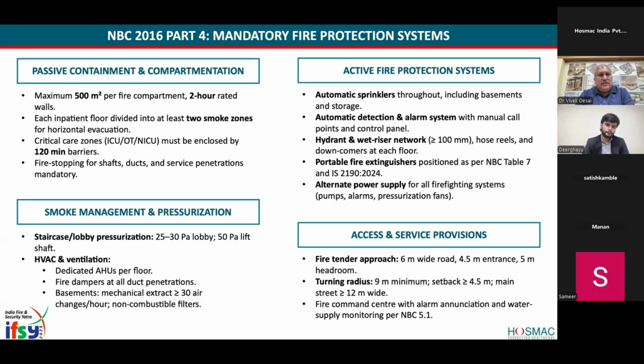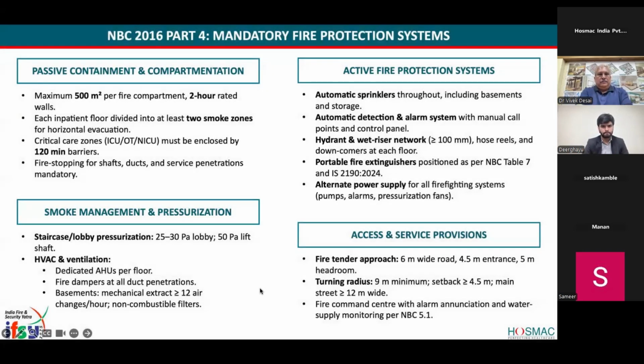So you should have fire dampers and all of that he mentioned. In basements, mechanical extract of more than 30 air changes per hour, non-combustible filters. Is there anything you want to say about basement exhaust, Satish? Yeah. So for basement exhaust, I think it is revised to 12 ACPH, not 30. Okay. Normally there will be smoke exhaust systems at 12 ACPH, and fresh air is also required as makeup for supplying oxygen to occupants. And normally the CFO keeps on asking, despite mechanical ventilation being given, for natural ventilation also, around 10 to 20% supplied naturally, so one has to keep a continuous open shaft for a basement. They normally insist on that, despite the mechanical ventilation being provided.